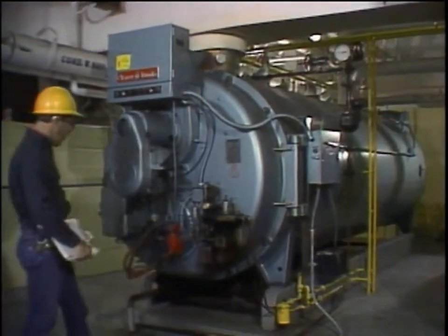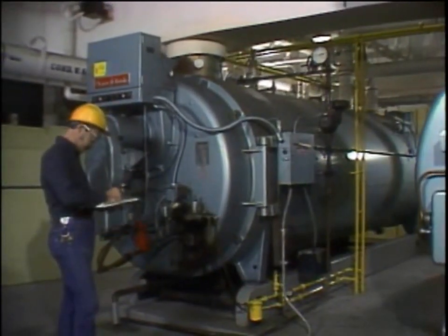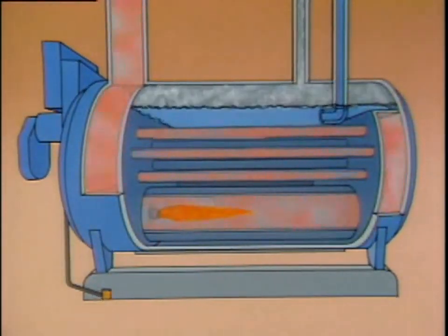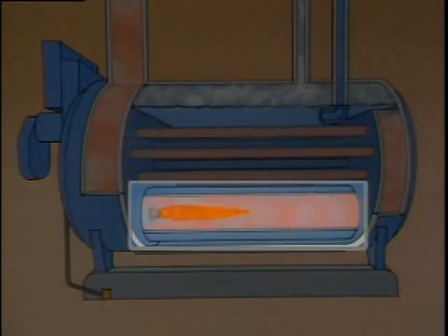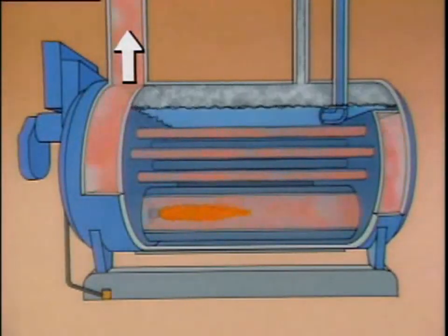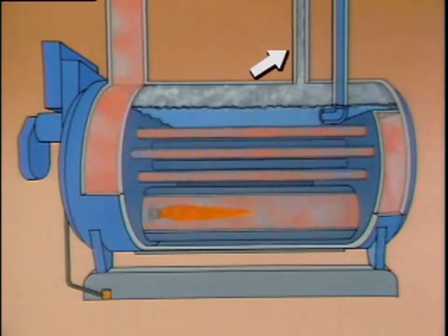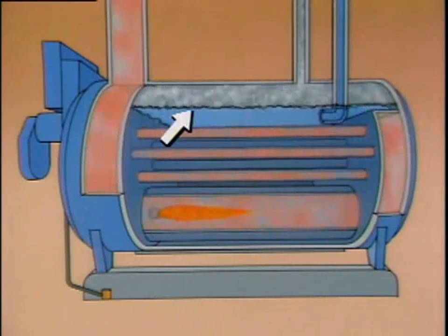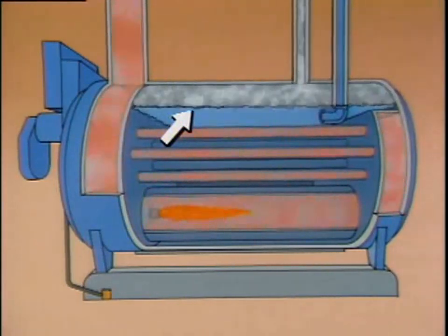Fire tube boilers route hot combustion gases through metal tubes. The tubes run through a shell filled with water. Fire tube boilers vary in design, but most operate under similar principles. A group of horizontal fire tubes routes combustion gases through the boiler. There's also an outlet for the gases, a feed water line, and a steam outlet line. During operation, water enters through the feed water line. The water level is maintained above the fire tubes to protect the tubes from overheating.